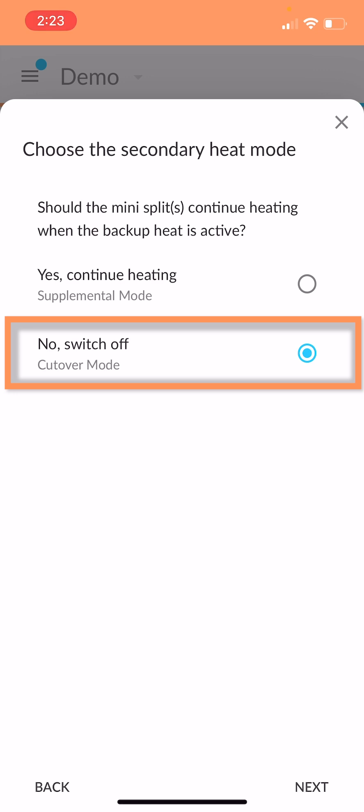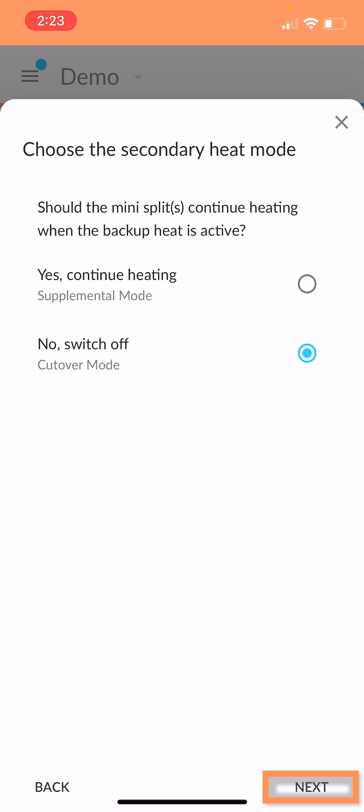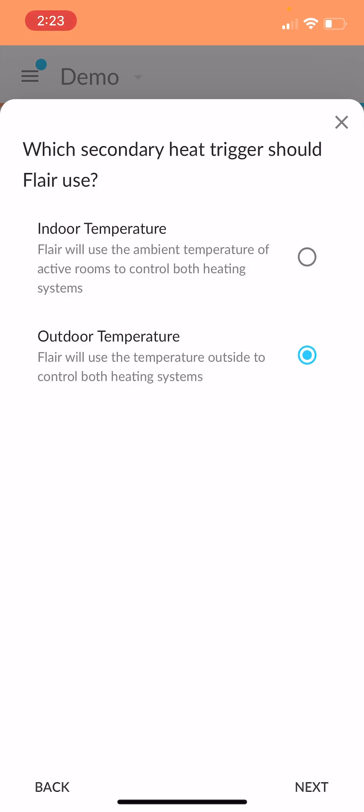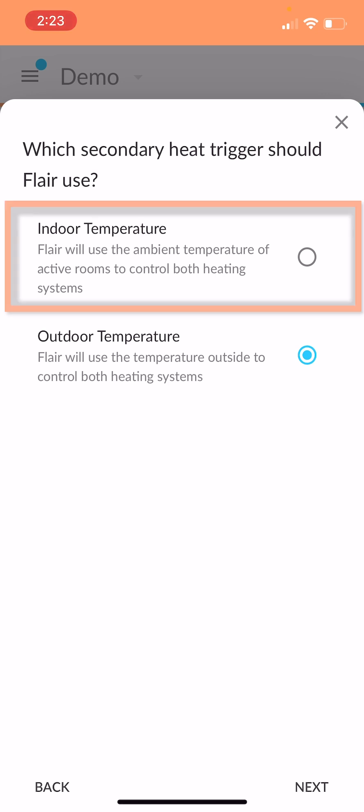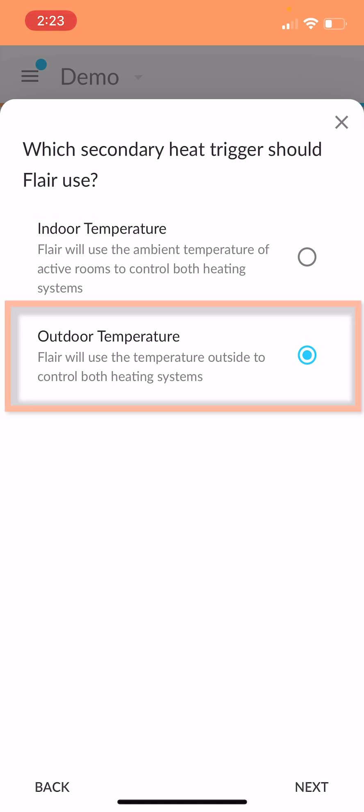That's what most state programs are looking for. So if in doubt, I'd recommend that. But you've got options. Okay, now another option you've got is what should cause you to change between stages. Indoor temperature is sort of like a droop option. It's not an uncommon pick, but I would say overwhelmingly, most people use the outdoor temperature.